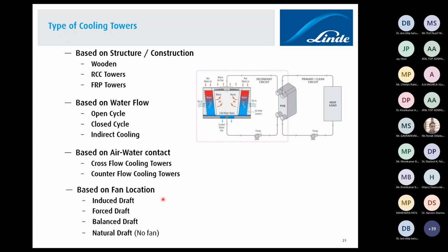So in that particular case only is forced draft used; otherwise nowadays induced draft is the economical one, and it is favoured in terms of maintaining the cooling tower height and from a power consumption point of view. And balanced draft is very rarely used, in a revamp or modification case where you already have an induced draft fan and you are just adding a few forced draft fans to facilitate some summer operation like that.